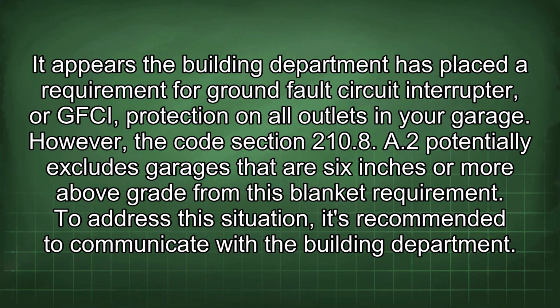It appears the building department has placed a requirement for ground fault circuit interrupter, or GFCI, protection on all outlets in your garage. However, the code section 210.8(A)(2) potentially excludes garages that are 6 inches or more above grade from this blanket requirement.